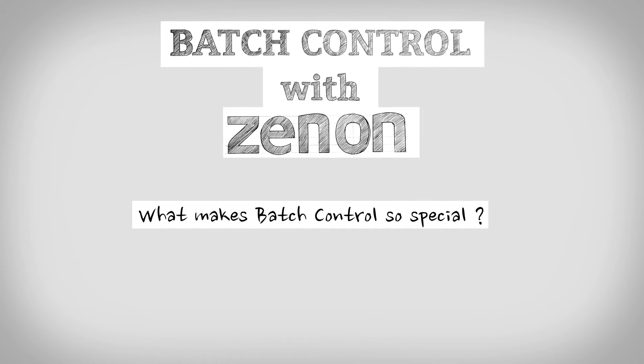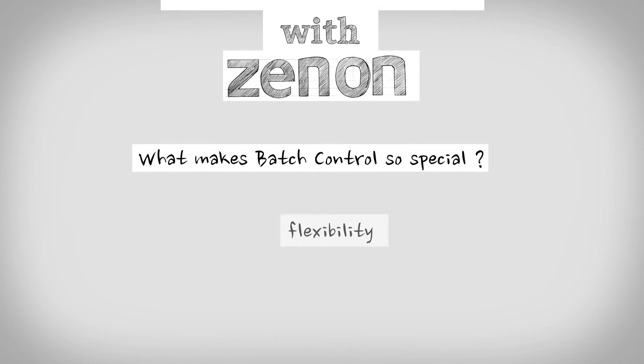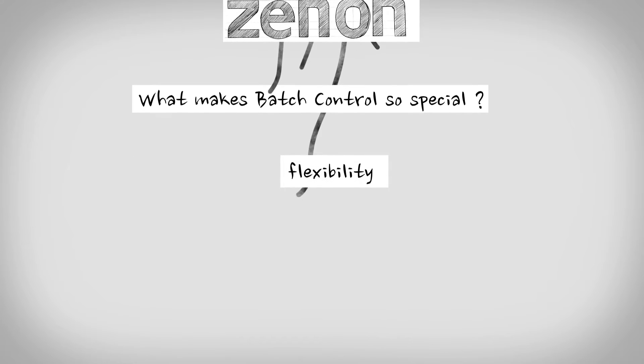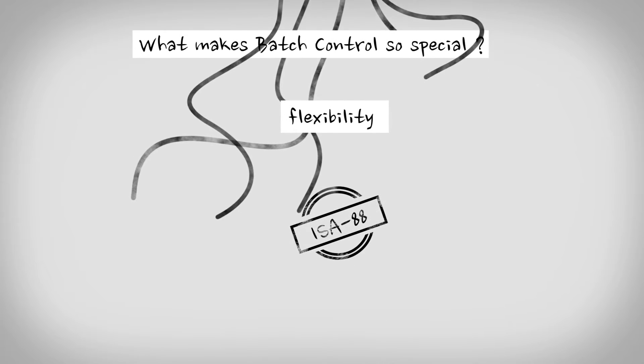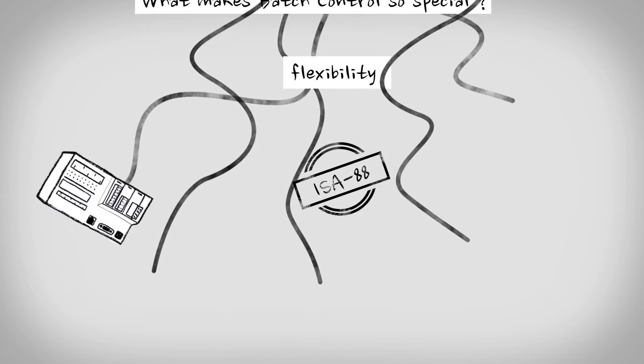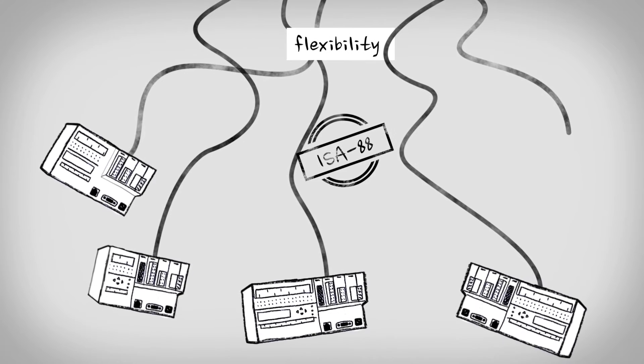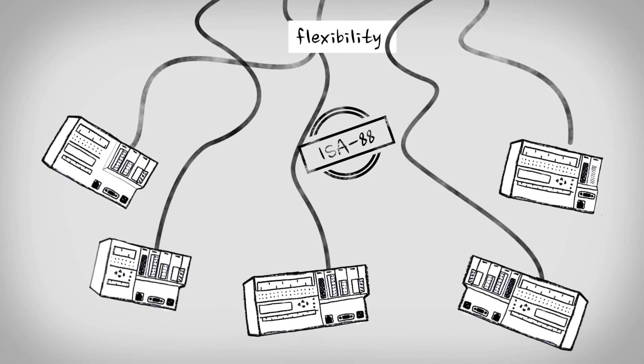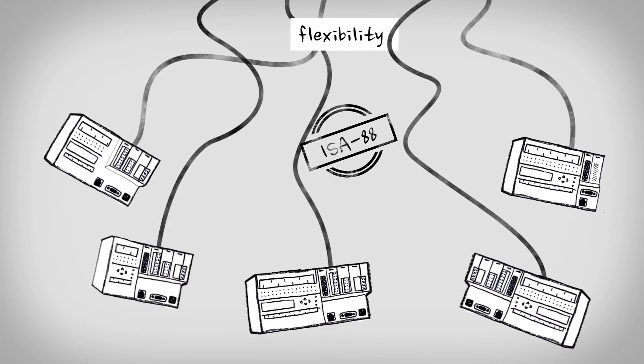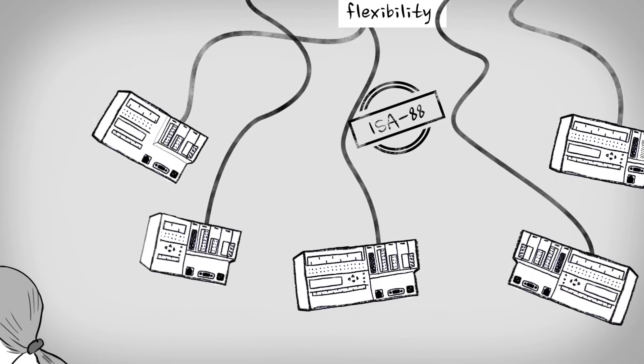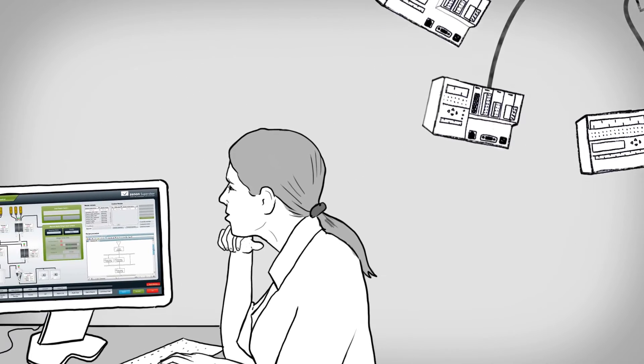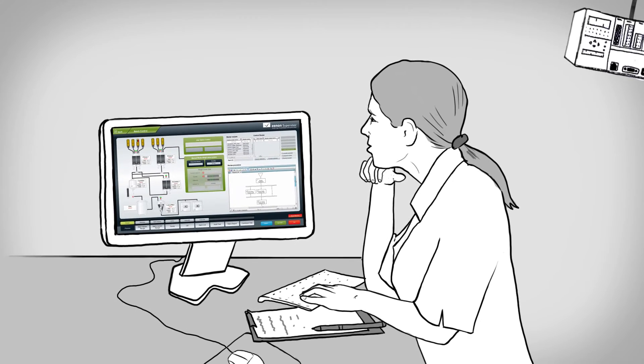First of all, flexibility is key. Batch control in zenon follows the ISA88 principle, as it separates the equipment and procedural control. Recipe evolution does not require revalidating equipment control. This gives more flexibility in managing continuous improvement at low risk.